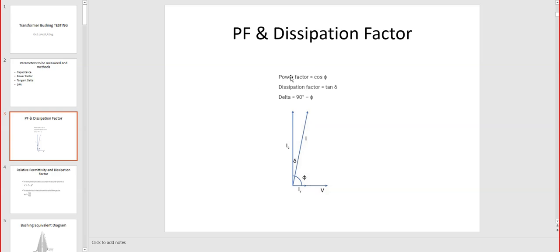So what is the power factor? What is the dissipation factor? Somehow they are used interchangeably. For both of them, we want them as low as possible, and there are recommended values from different manufacturers: what they should be when you receive a new bushing, and how far you can go with the bushing until a major change happens, and then you declare that bushing non-repairable. You need to take it out of use because these values get over the limit that is acceptable for that manufacturer. Also, for a smaller change, they recommend some countermeasures for a smaller variation of these two parameters. So again, power factor and dissipation factor.